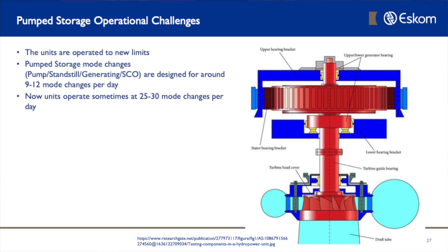Let's look at the pump storage first. If we look at the pump storage unit, we operate in 4 modes. We can operate at standstill, where we're not moving or doing anything. We can go into pump direction, and we can go into generating direction, where we have to come back to standstill, change direction, and go into pump or into gen. Then, as I mentioned, synchronous condenser operation, where we put air into the turbine and run as reactive power - that's the 4th mode.